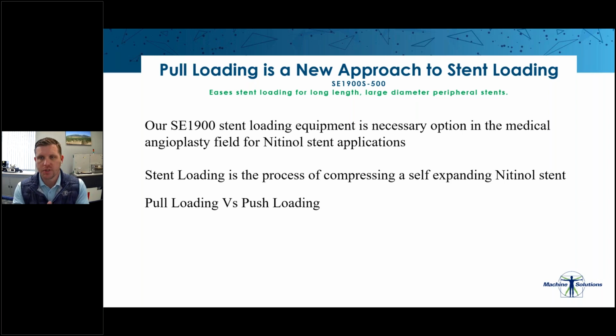Push loading is the traditional method of stent loading and is still the preferred method for smaller diameter stents, typically less than 10 millimeters of open diameter. For this method, the stent is crimped into the segmental compression head without the delivery catheter underneath. A push quill is used to push on the distal crown structure of the stent while under radial compression. Using crimp pulse technology to reduce the stiction, the stent is pushed into the introducer sheath, which is clamped proximally of the crimp head. Once loaded into the introducer, the delivery system is then moved into place under the stent that remains in a compressed state. This method works well for small diameter stents, less than 10 millimeters of non-compressed OD.